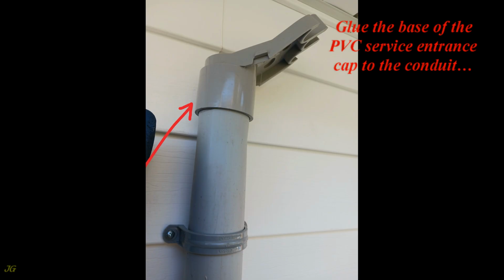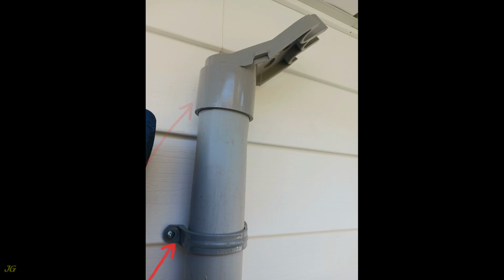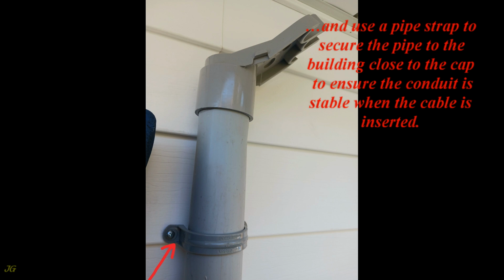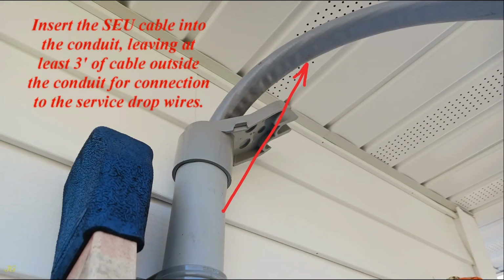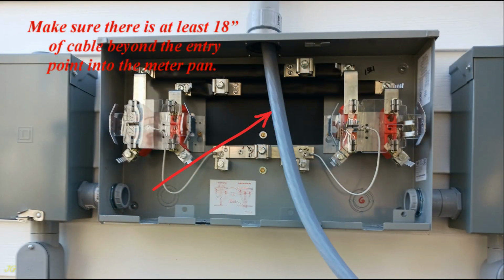Glue the base of the PVC service entrance cap to the conduit, and use a pipe strap to secure the pipe to the building close to the cap to ensure the conduit is stable when the cable is inserted. Insert the SEU cable into the conduit, leaving at least 3 feet of cable outside the conduit for connection to the service drop wires. Make sure there is at least 18 inches of cable beyond the entry point into the meter pan.